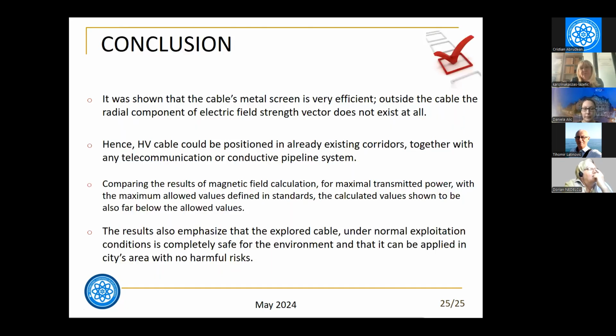As a conclusion, we can say that we showed that the cable metal screen is efficient, and outside the cable, the radial component of electric field strength vector does not exist at all. Hence, the high voltage cable could be positioned in already existing corridors together with any telecommunication and conductive pipeline system. Comparing the results of magnetic field calculation for maximal transmitted power with the maximum allowed values defined in standards, the calculated values show to be also far below the allowed values. The results also emphasize that the explored cable under normal exploitation conditions is completely safe for the environment and that it can be applied in city areas with no harmful risks.